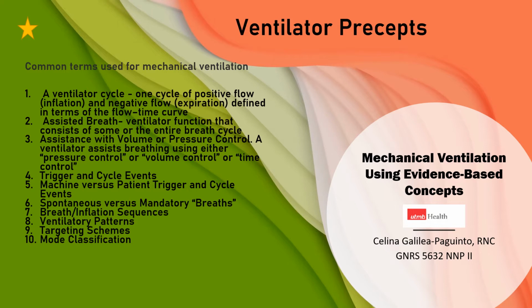Patient triggering is where the patient prompts the ventilator to deliver the inflation. Ventilator triggering originates from the machine using a time signal. Patient cycling means ending the inflation based on the signals representing the patient-determined components. And ventilator cycling means ending inflation independent of signals representing the patient-determined components.